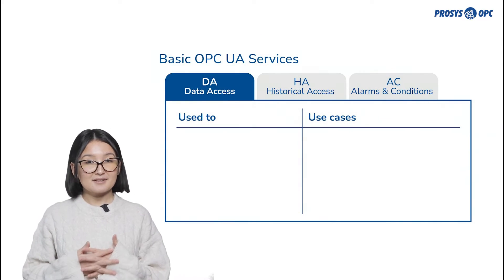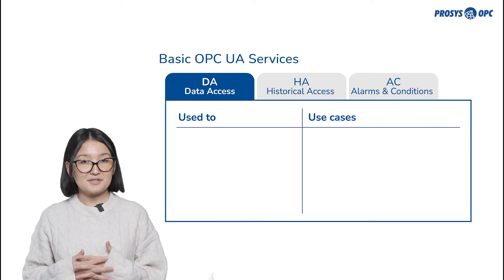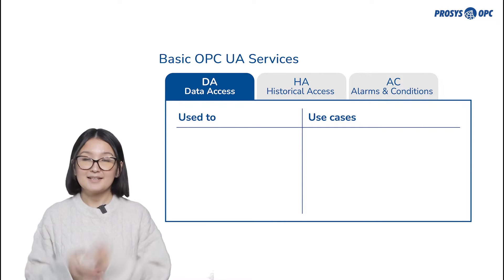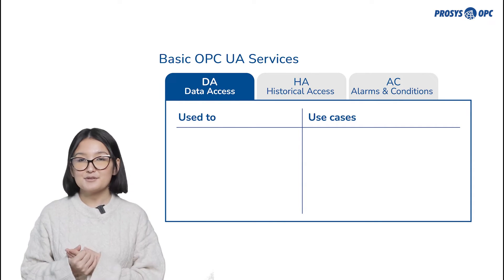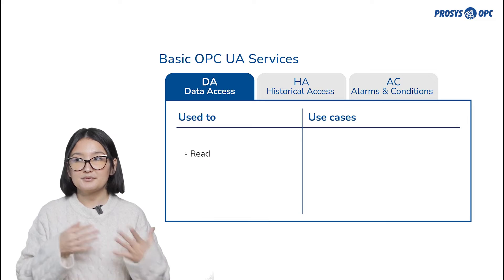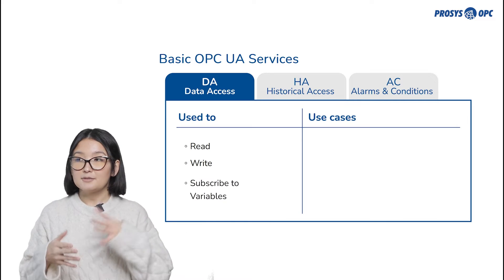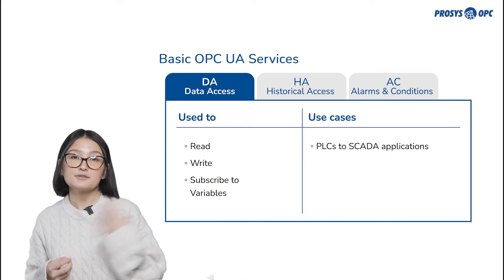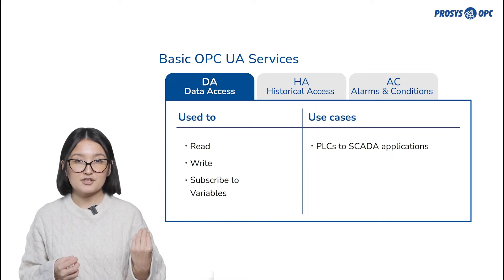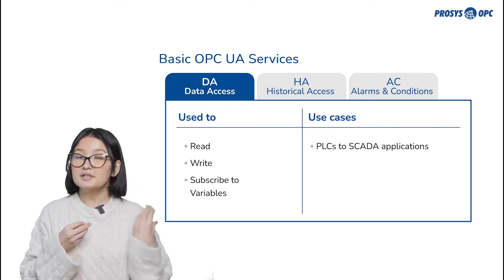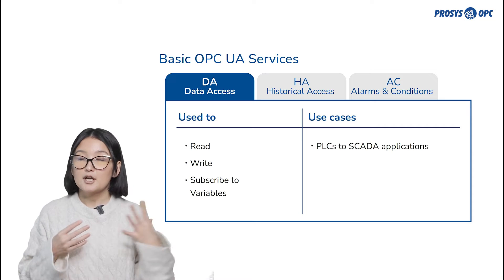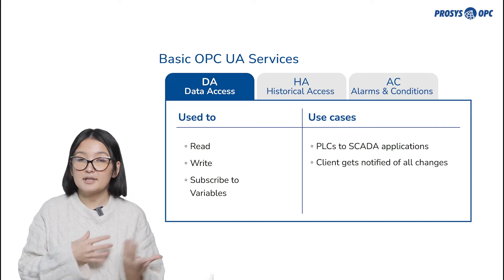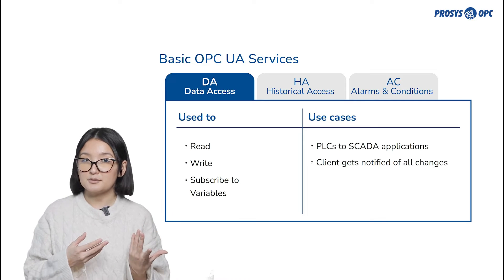By default, there are three basic data models in OPC UA, and those are pretty similar to OPC Classic. Data Access, or DA, is used to read and write current values. The most common use case is to read tags from PLCs to SCADA applications. Another use case is to create subscriptions, which means that the client gets notified about any possible changes in the values.